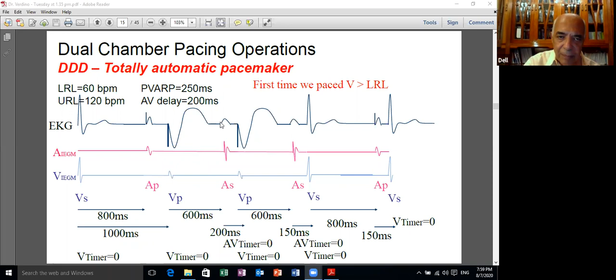Here again, we are pacing in the atrium, and then 200 milliseconds, nothing happened. Then we throw a spike into the ventricle, which brings the V timer to 0 and starts to count 800 milliseconds. Before the lapse of the 800 milliseconds, we felt an atrial activity sensed by the atrial electrode, and then we started to count 200 milliseconds, which is the AV interval. Nothing happened. We throw an impulse here and activate the ventricle.